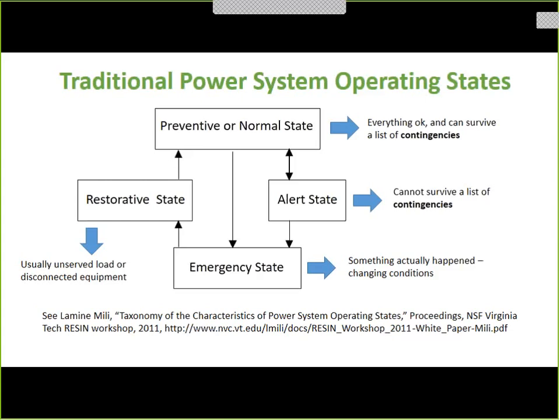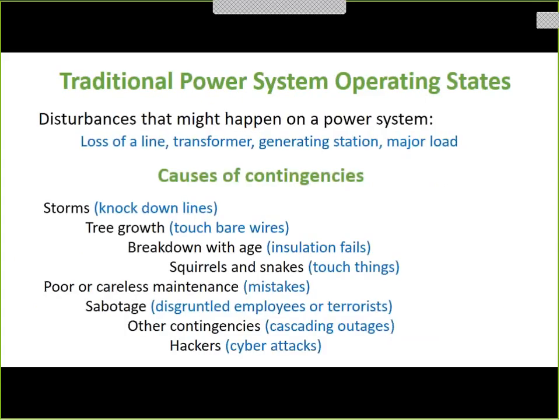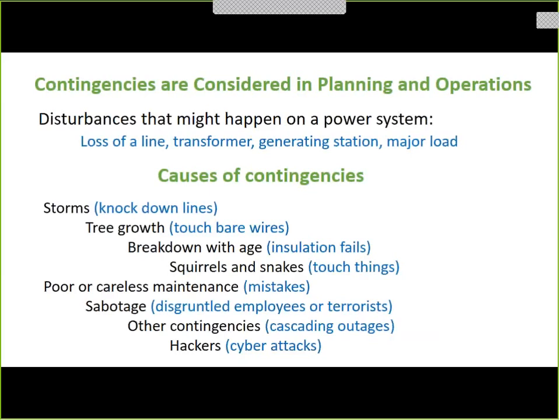Once you have gotten everything to settle down, then you have to put the grid back together. So that usually means adding some load back in that somehow got disconnected, adding a line back in that got switched out, whatever it takes to get back to the normal state. Okay, contingencies are considered both in planning and operations. So I call it operational reliability, but when you're planning a new grid for the year 2030, you have to propose all the contingencies for the year 2030. So both planners and operators use this stuff.